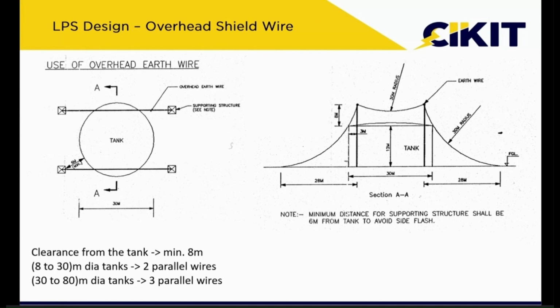Then the third method is by using overhead shield wire. The drawback of the first two methods was that the center portion of the tank was still unprotected. If you want to protect the entire tank area, then we have to go for overhead shield wires. The shield wires will be laid between the tank poles, so there will be some conductors on the center portion also. Here you can see, since we have these two poles along the internal, by using the rolling sphere method we can observe that the tank is protected along the entire area, even the center portion.